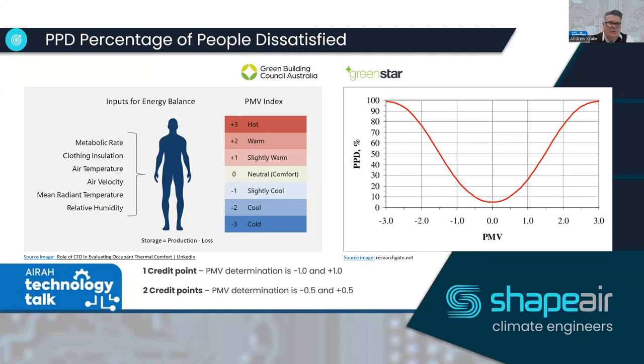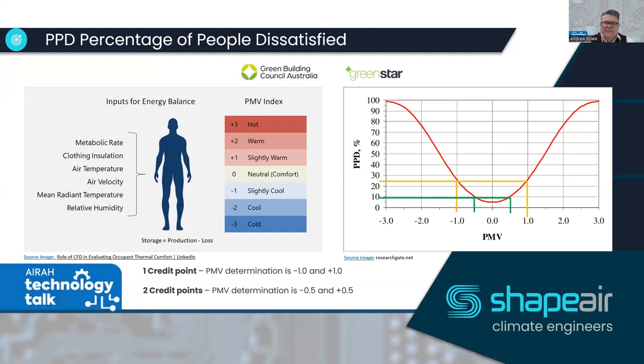What we're aiming for is to have everybody in the neutral zone. For one Green Star credit point you need to be between minus one and plus one, which means the percentage of dissatisfied people needs to be below 25%. For two credit points — between minus 0.5 and plus 0.5 — you need below 10% dissatisfied. Going further, you can achieve around 5% dissatisfaction in the neutral zone.